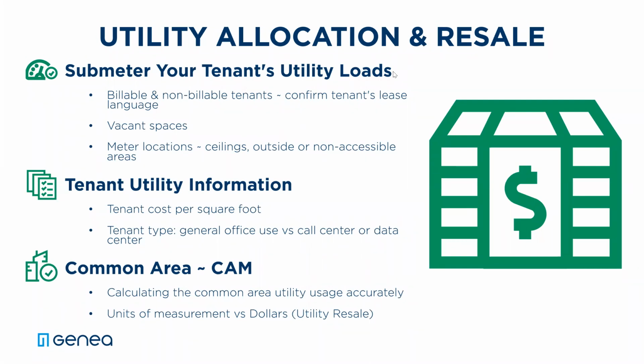We've come across cases where we've seen a vacant meter jump up in usage. We contact the property management company and we find out that a leasing agent has shown the space and left all the lights on. Or in some cases, we see that there's an increase in usage on both the lighting and receptacle meter, contact the property management company and discover that a tenant had moved in that we hadn't received that information on. So by submetering all of your spaces, it gives you much more valuable information as a whole.